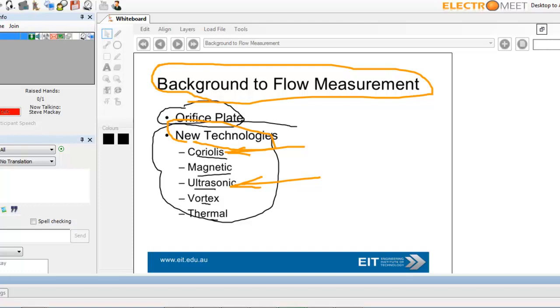Disadvantages, forget about gas or steam. It's not going to measure that. Petroleum liquids, no go because there's no conductivity. And you can get a problem with coating on your electrodes, which means they need to be maintained.